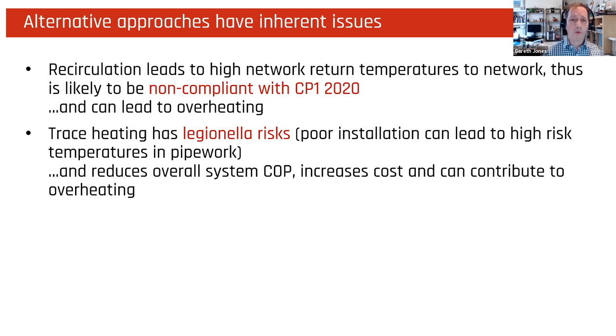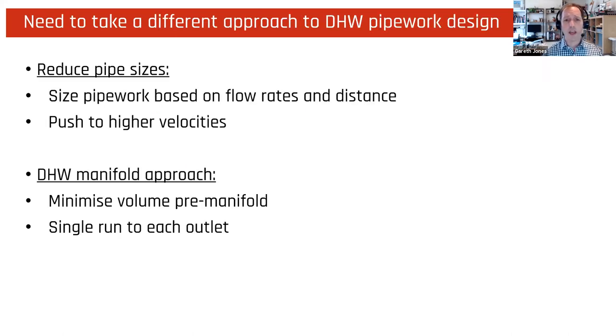So what we need to do is move away from that and actually look at how we design tertiary domestic hot water pipework. And we're suggesting we take a different approach. First thing, we need to reduce pipework sizes. So size pipework based on flow rates and distance, and push to higher velocities. And then we'd also really strongly recommend moving to a domestic hot water manifold approach, where you're minimizing the volume pre-manifold and then running a single pipe to each outlet and sizing that pipe to the flow rates that you need for that outlet.